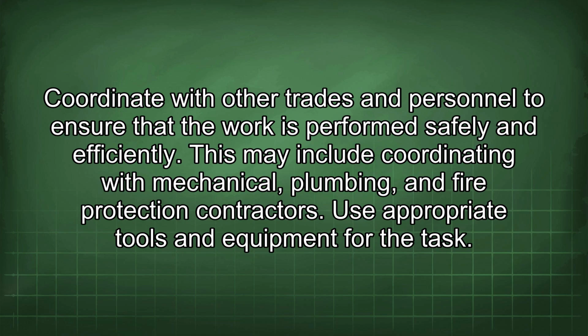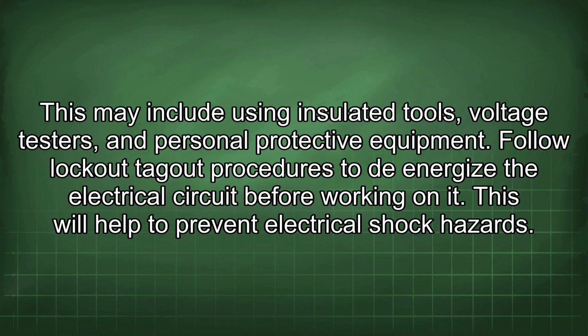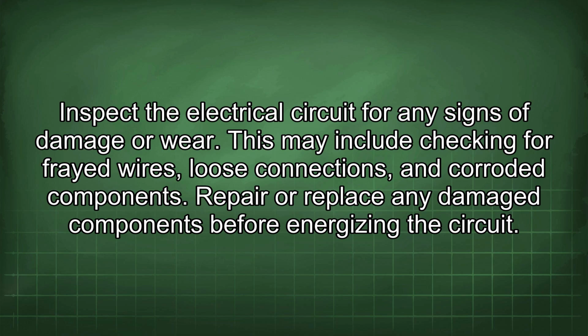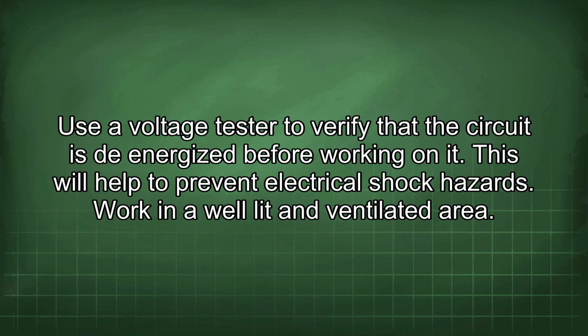Use appropriate tools and equipment for the task. This may include using insulated tools, voltage testers, and personal protective equipment. Follow lockout-tagout procedures to de-energize the electrical circuit before working on it. This will help to prevent electrical shock hazards. Inspect the electrical circuit for any signs of damage or wear. This may include checking for frayed wires, loose connections, and corroded components. Repair or replace any damaged components before energizing the circuit. Use a voltage tester to verify that the circuit is de-energized before working on it. This will help to prevent electrical shock hazards.